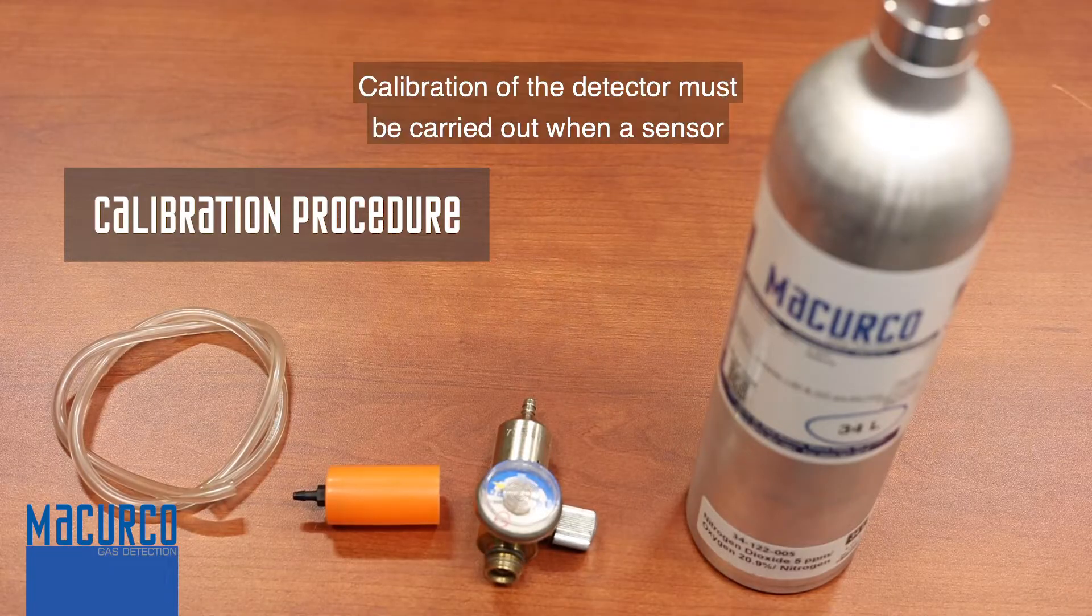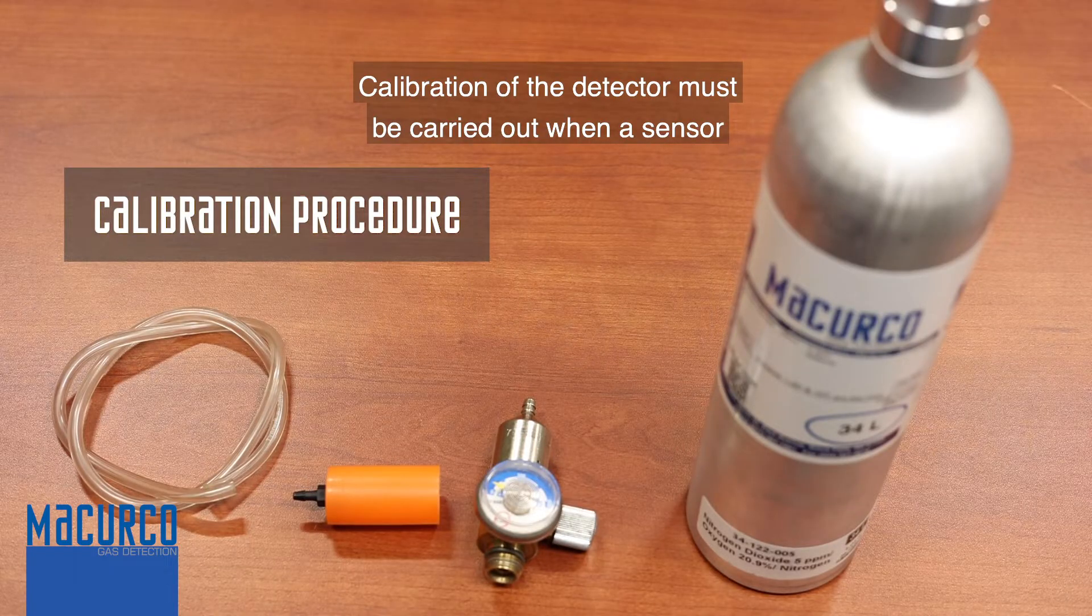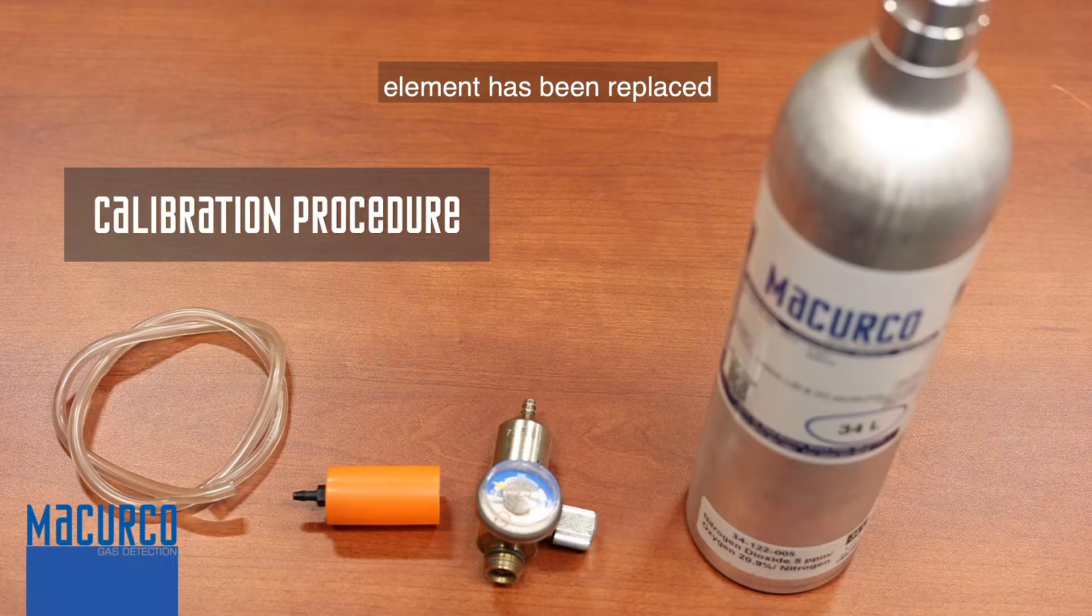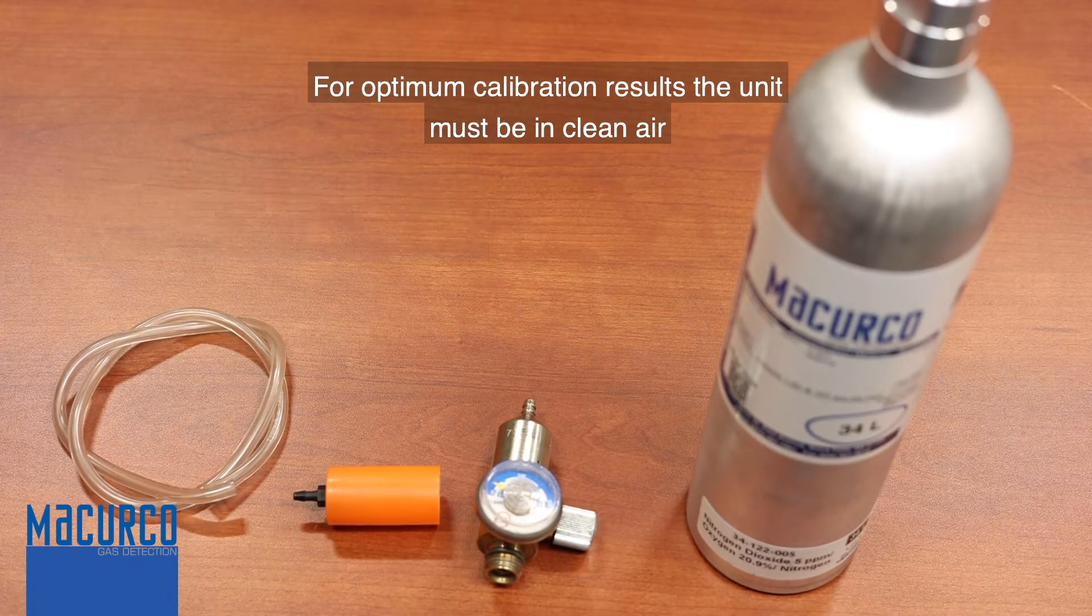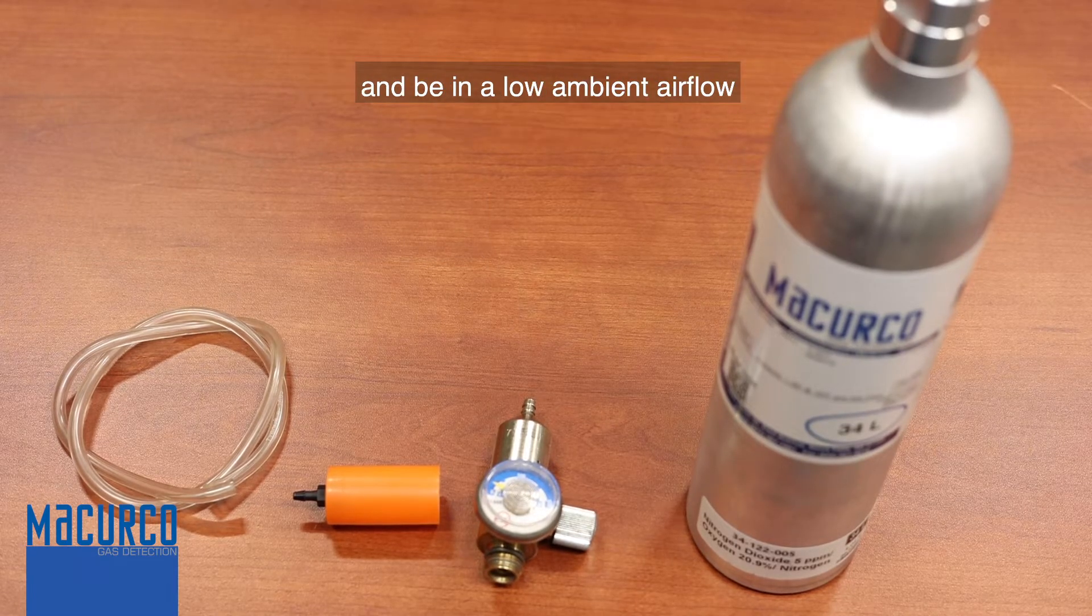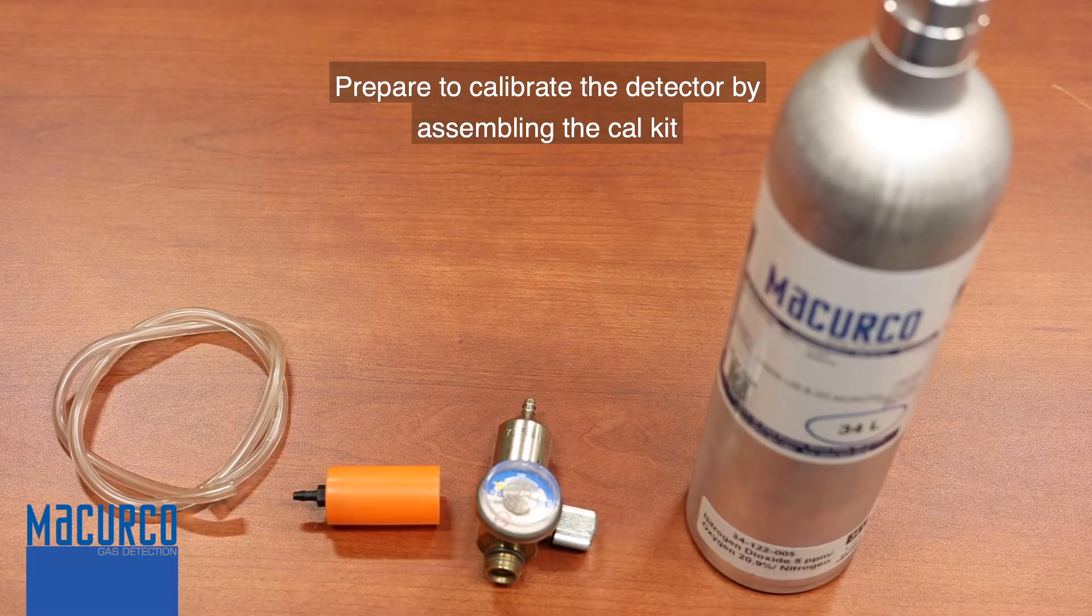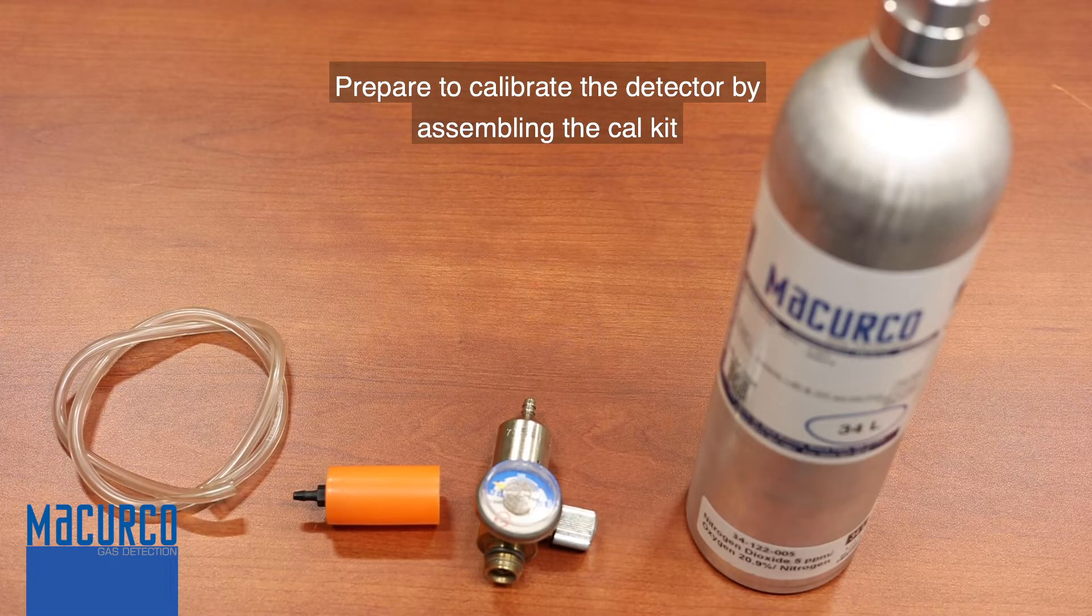Calibration procedure: Calibration of the detector must be carried out when a sensor element has been replaced. For optimum calibration results, the unit must be in clean air and be in a low ambient airflow. Prepare to calibrate the detector by assembling the cal kit.